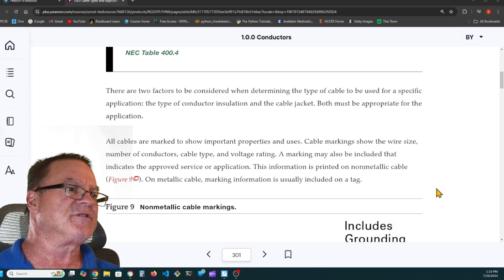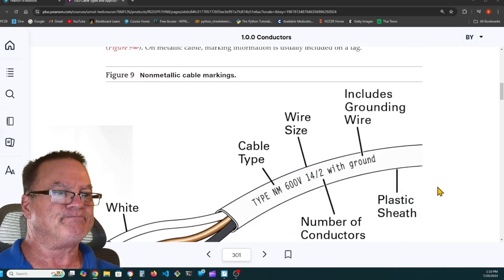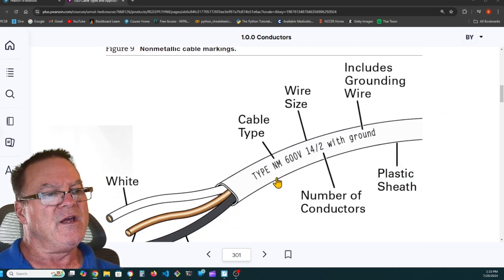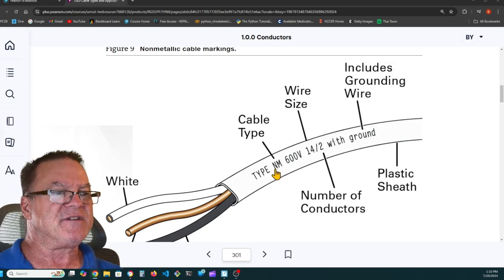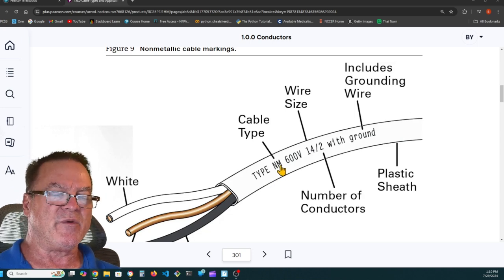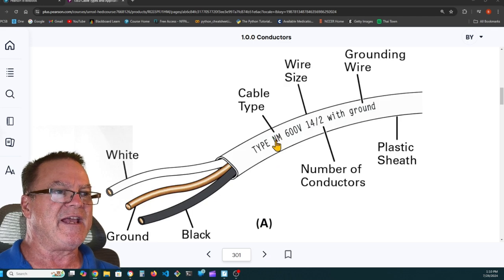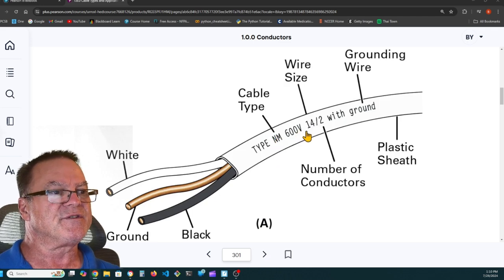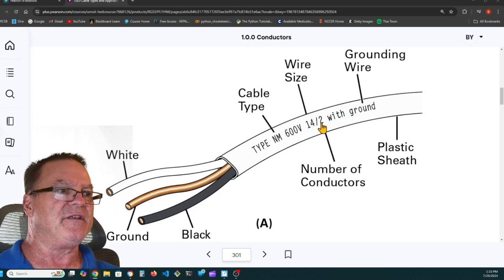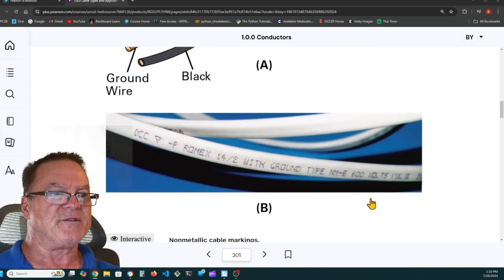Marking information is usually included on a tag. So here's type NM. It's non-metallic sheathed cable. This is what we usually call Romex. That's the cable type. It's good for 600 volts. The wire size is 14 gauge. There are two current carrying conductors in the sheath with a ground. So that's the black and the white and the bare ground. And then this is a plastic thermoset sheath that surrounds it.